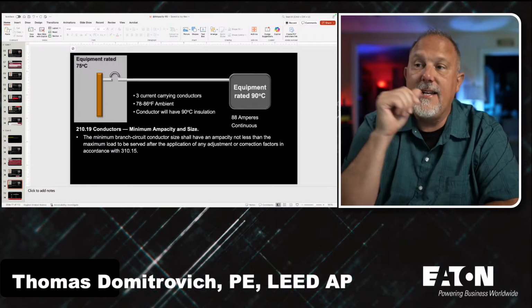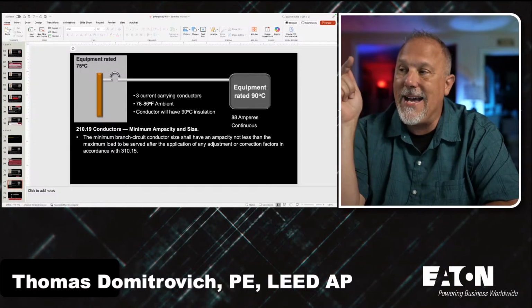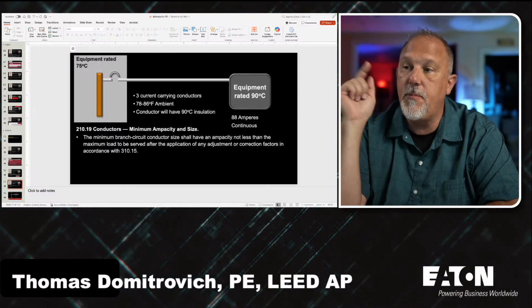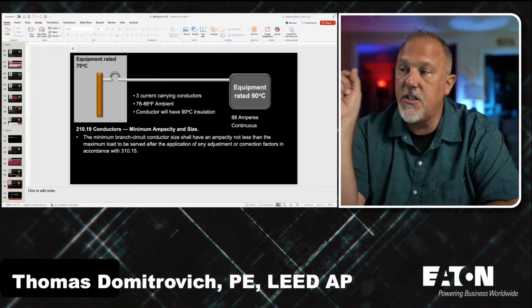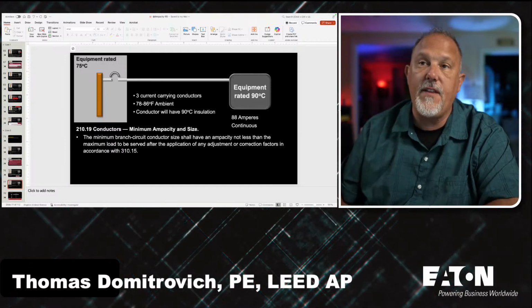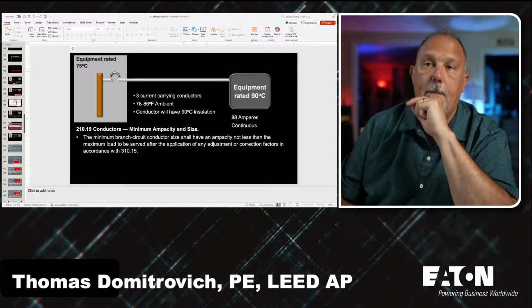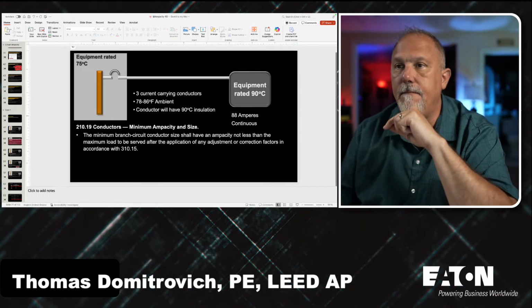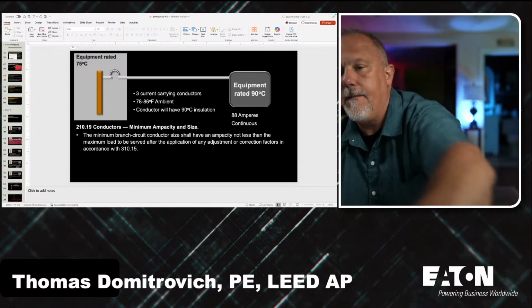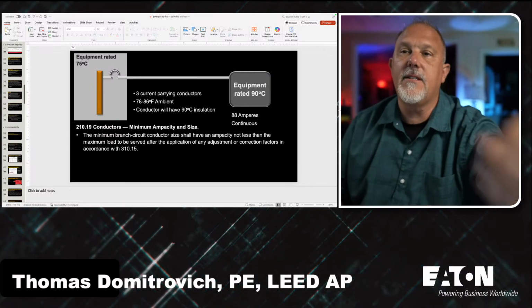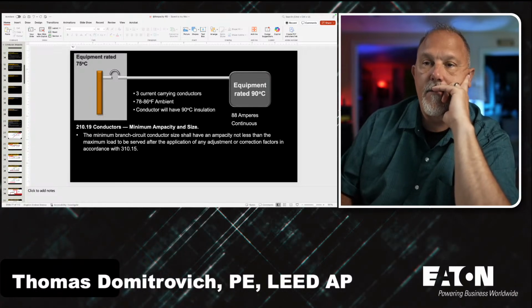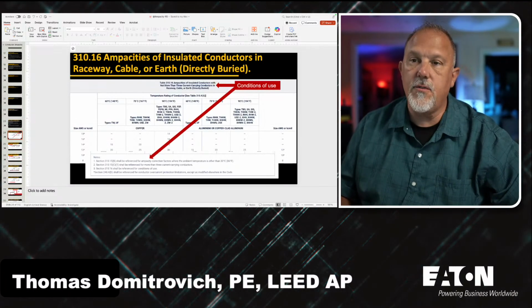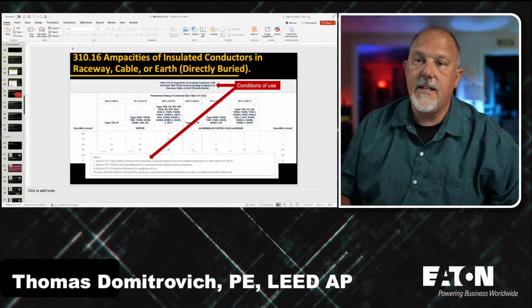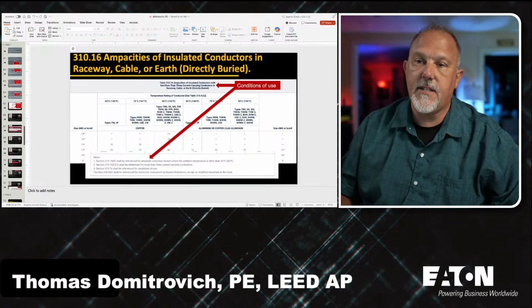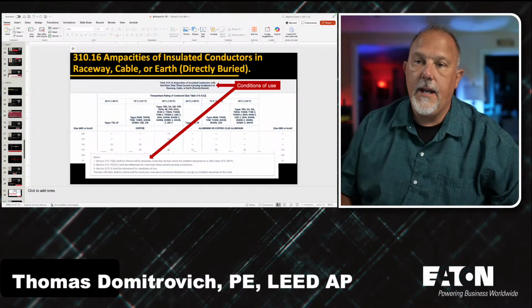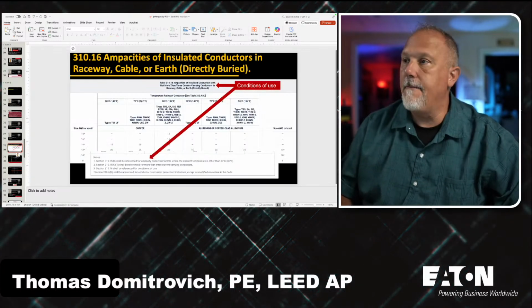Now, the second one says the minimum branch circuit conductor size shall have an ampacity not less than the maximum load to be served after the application of adjustment or correction factors in accordance with 310.15. Now, if we recall, I'm going to go back up. What slide am I on? Alan, what slide am I on? I'm on slide 77. So we're going to come up to here, slide 77. I'm going to do a Control C, and I'm going to come down here to slide 78, Control V.